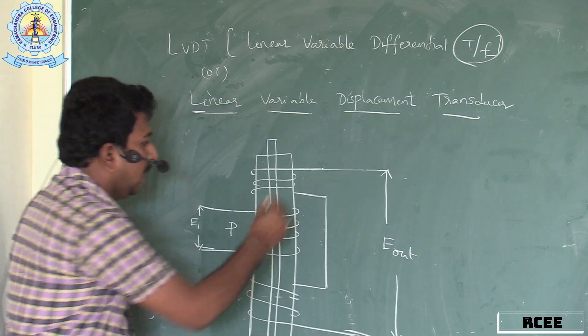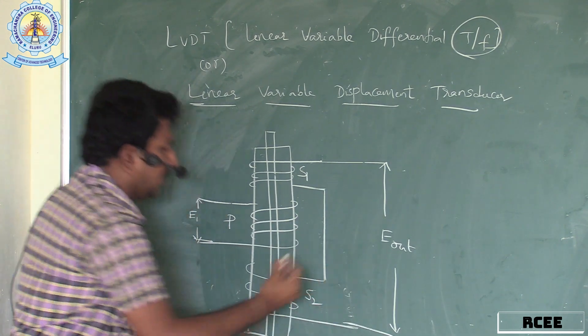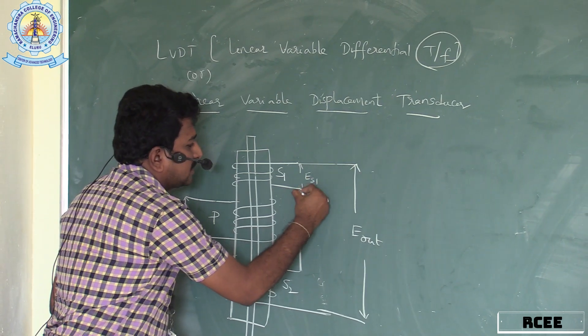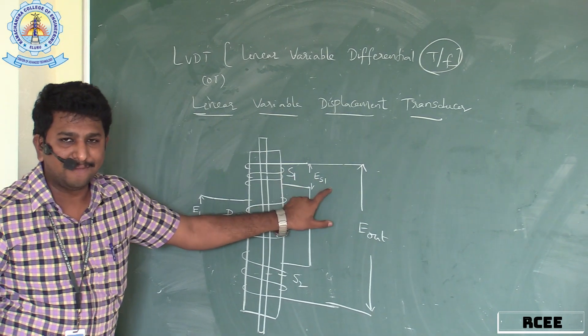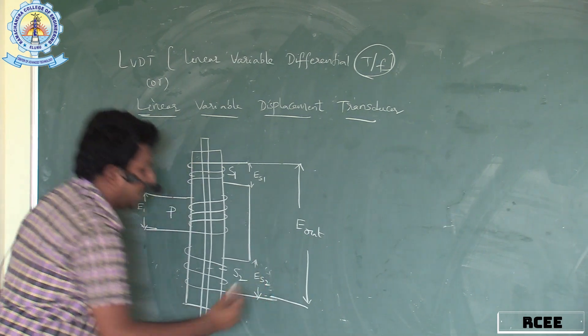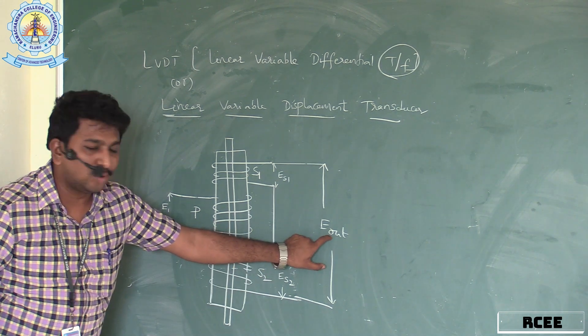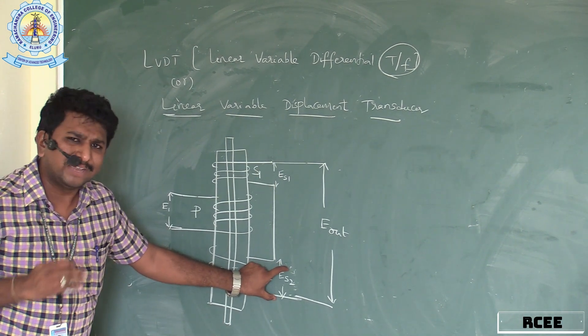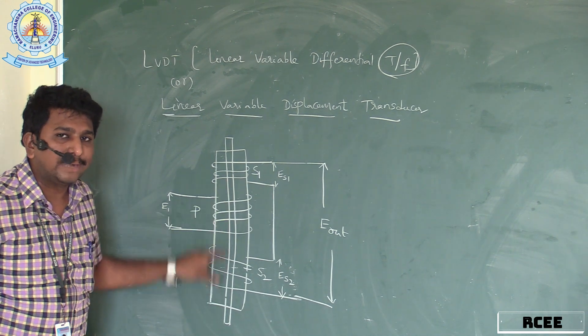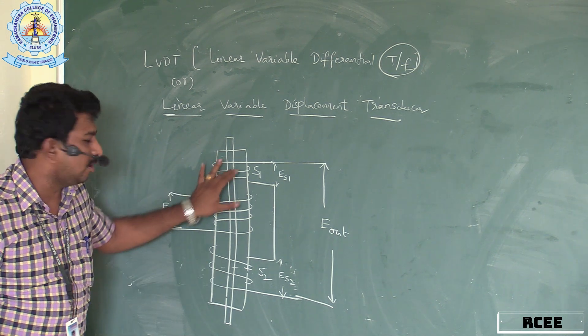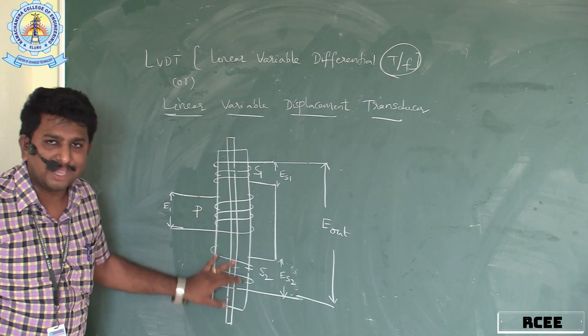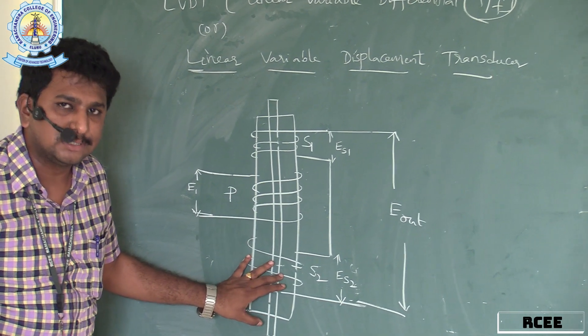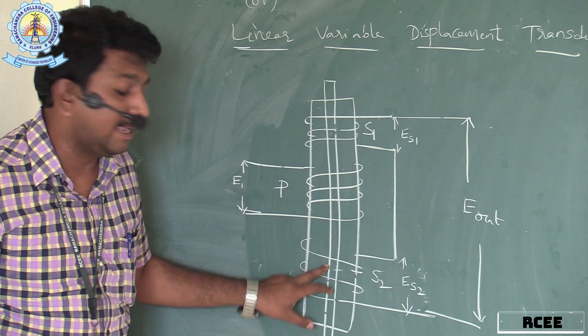LVDT consists of two secondary windings: S1 and S2. ES1 stands for output across secondary winding one, ES2 stands for output across secondary winding two. The final output voltage Eout is the difference between ES1 and ES2. These two secondary windings have equal numbers of turns and are connected in series opposition.